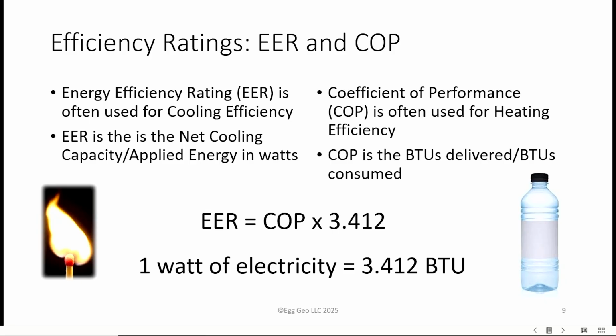So if you put 1 watt of electric heat into a bottle, it will give you the equivalent of 3.4 matchsticks worth of energy, or 3.4 BTUs. The energy efficiency rating is used normally in the United States for cooling. The rest of the world uses COP for both cooling and heating. COP is the easiest to understand. EER mixes units, and it's a manufactured rating to complicate things so they're not easily understandable. So I'm not going to talk much about EERs. I'm going to stay with COPs, since most everybody in the heat pump world stays with COPs these days.